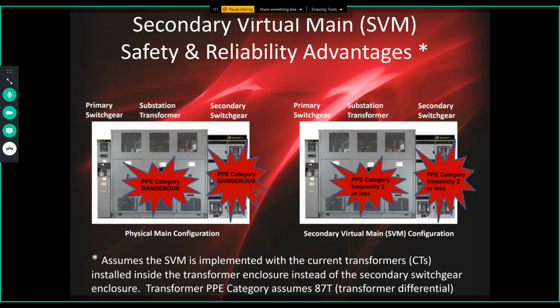And as compared to a secondary virtual main, in this particular example, in order to get the transformer down here, in addition to a secondary virtual main, we needed to add 87T, or transformer differential protection. And then the secondary virtual main frequently, usually, and again, you have to model this, delivers less than 8 calories per centimeter squared at the IEEE 1584 working distance.